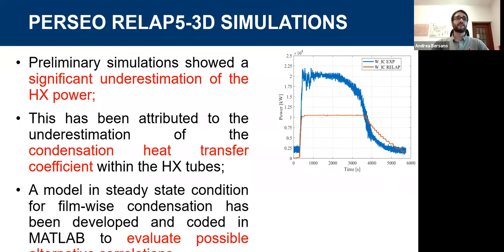After analysis, this underestimation has been attributed to the underestimation of the condensation heat transfer coefficient within the heat exchanger tube. This is exactly related to the different operating conditions between active and passive systems. In this case, in order to reduce the frictional pressure losses, because the driving force is lower in passive systems, the tubes have a relatively high diameter, and therefore the steam velocity within the tube was relatively small. For this reason, the code was not able to correctly predict the heat transfer coefficient.